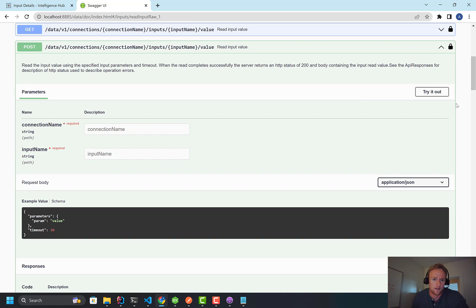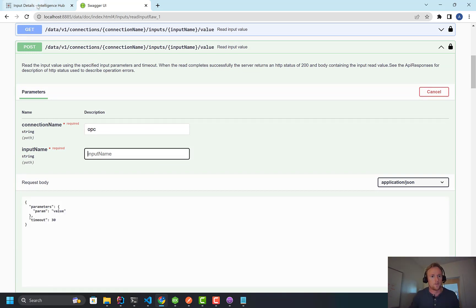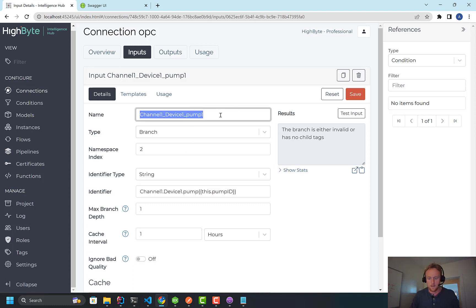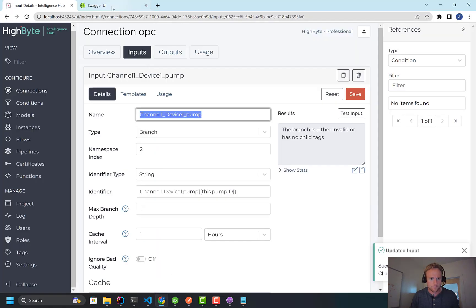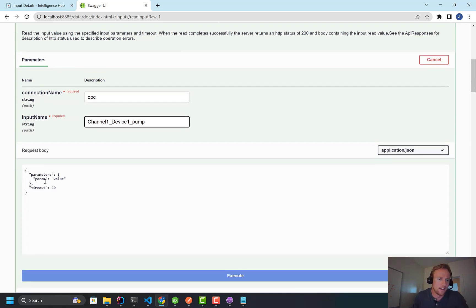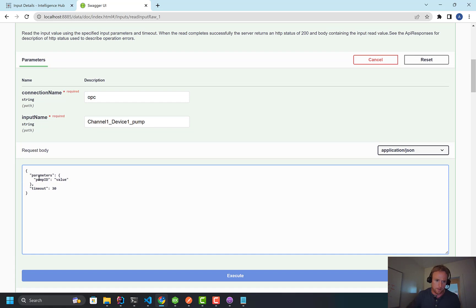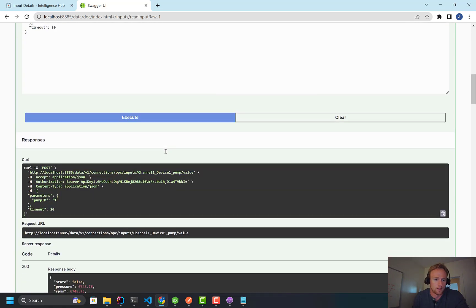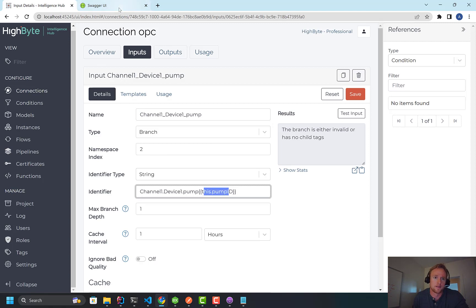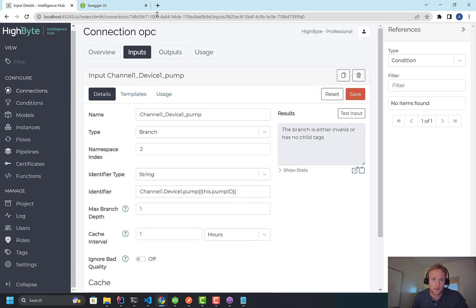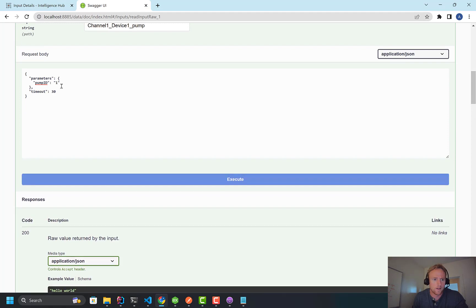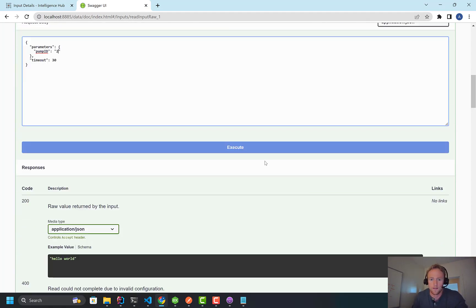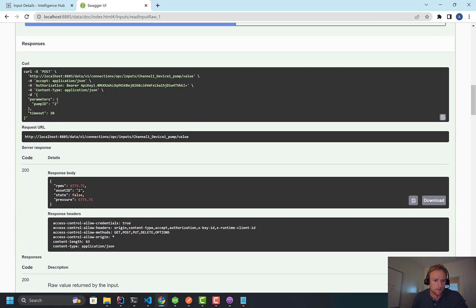So this is going to do a read. Let me try it out. OPC. I want to use the input name, which in this case is, I'm actually going to change it just to pump, right? And in here I can pass the parameters. So I'm going to, this is just key value pairs. So the pump ID, let's say is one. And I'll execute that. And what this is going to do is it goes in and does the read and that pump ID gets replaced, right? And that's the address into the OPC server. So now what's going to come back is pump one. Likewise, if I come out and run the same query and I increment to pump two, now pump two comes back, right? With a different asset ID.